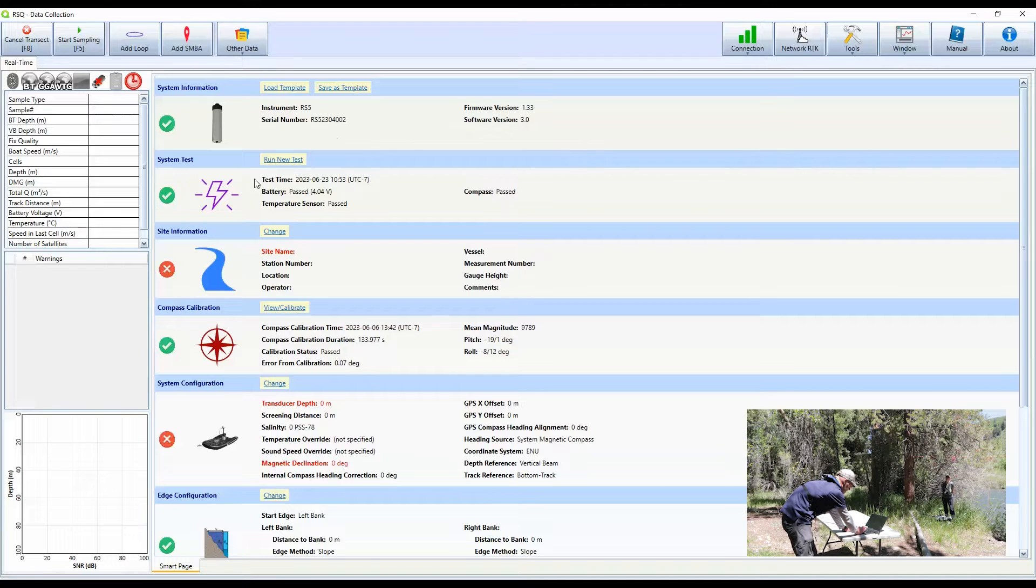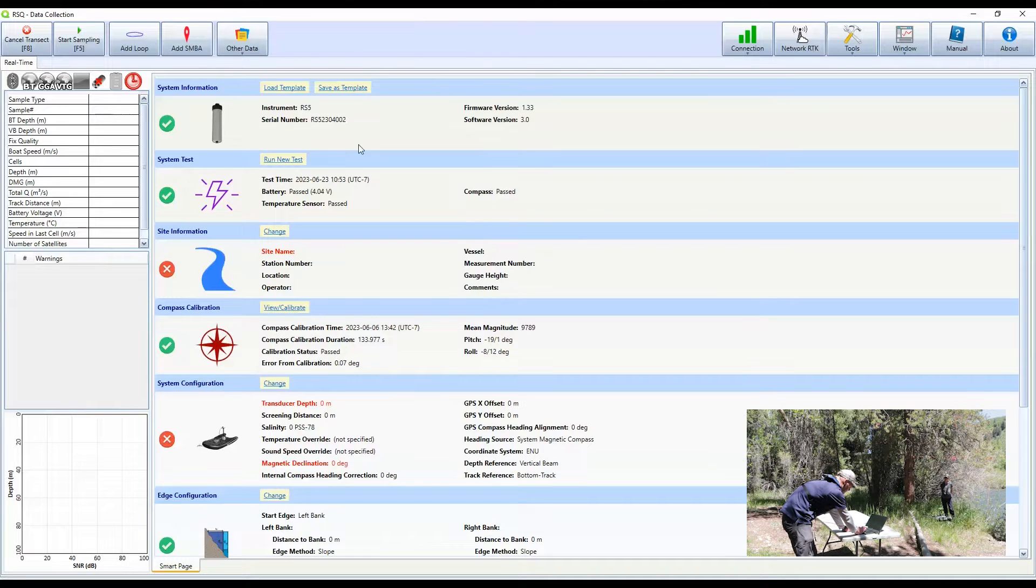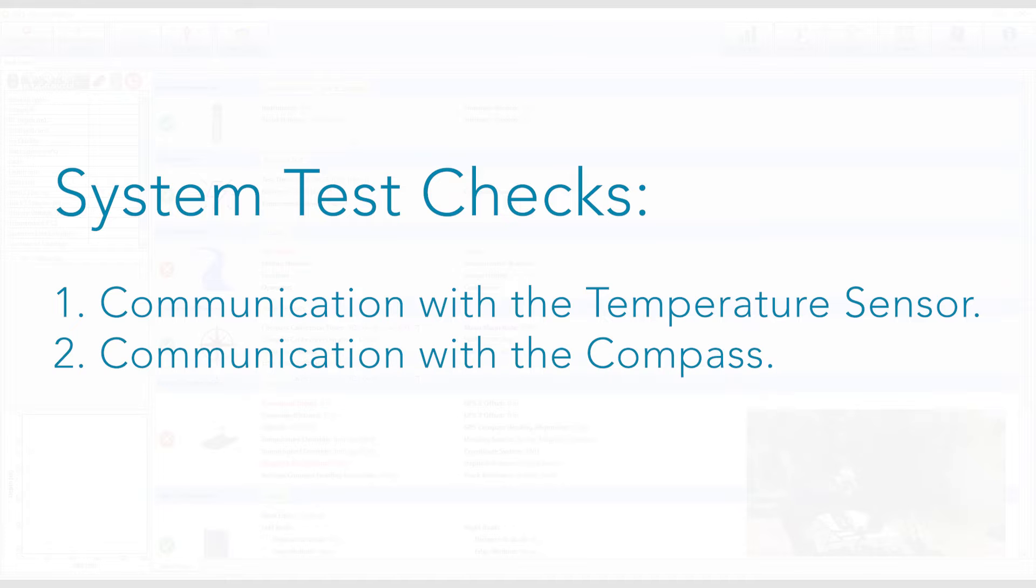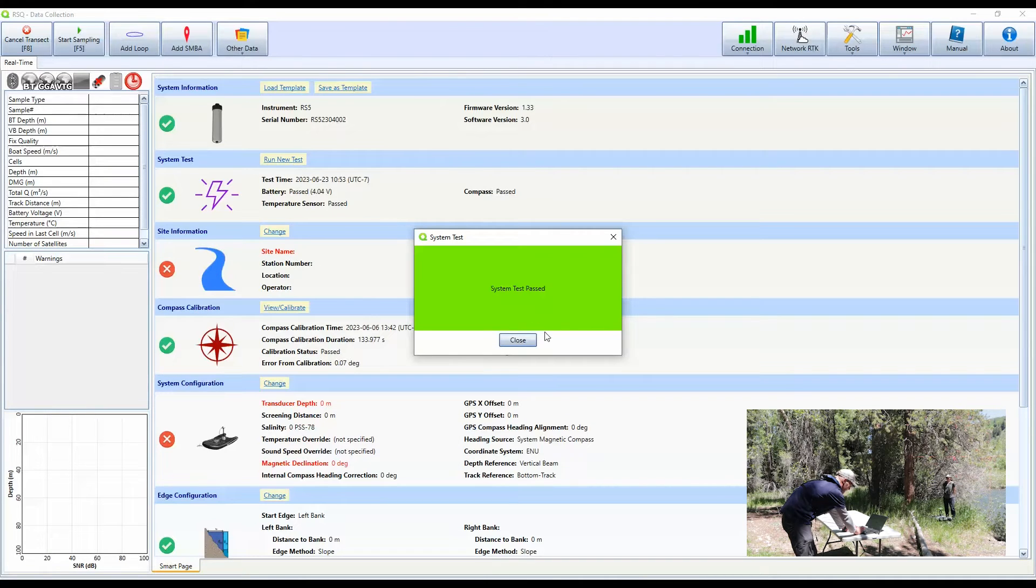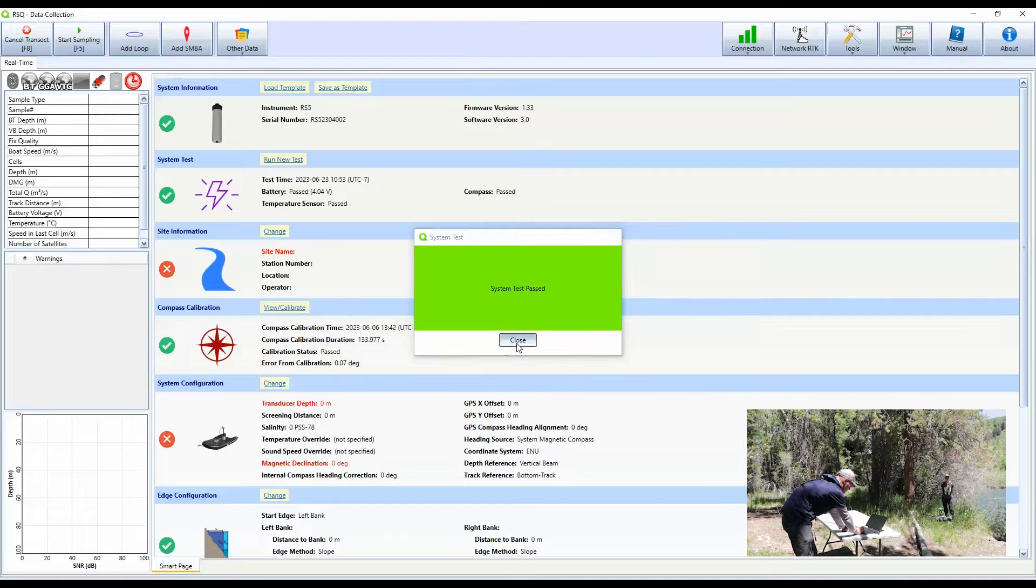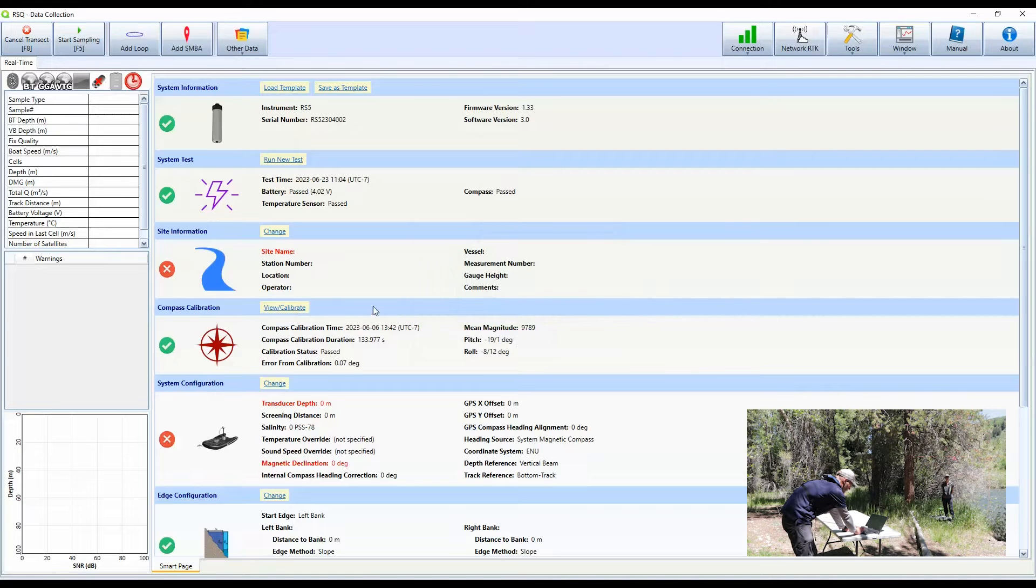The next section is system test. The system test is going to check communication with the temperature sensor, the compass, and it's also going to check the battery voltage. If we have issues with any of those three things, we'll receive a warning once the test is complete. We have the system test passed. So I'm going to close that out.